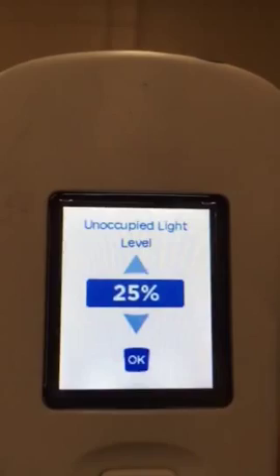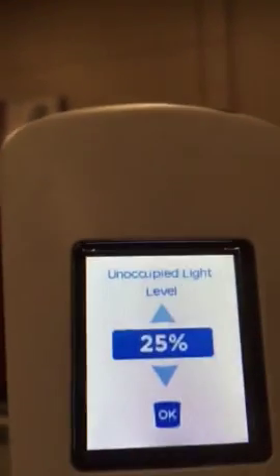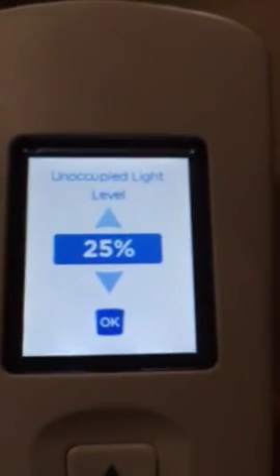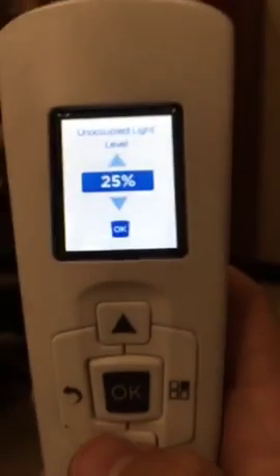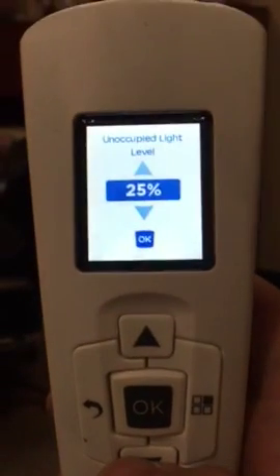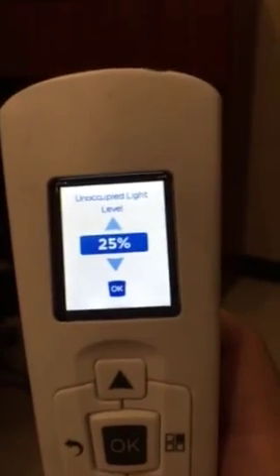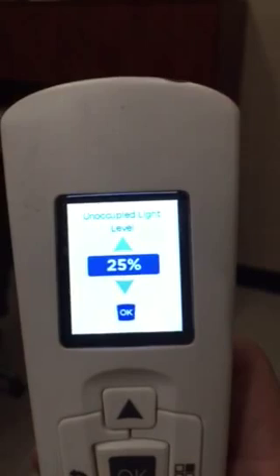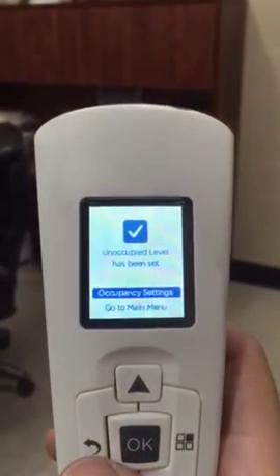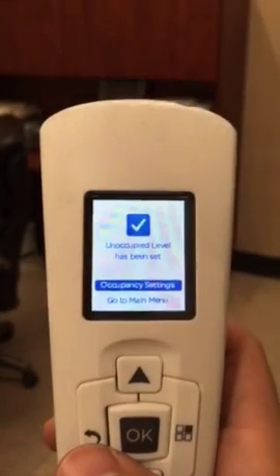It's going to say 'Unoccupied Light Level.' You'll also notice the four lights are dim, which means this has selected them. The unoccupied light level was set at twenty-five percent, to go into that after five minutes of no activity. But I came here about fifteen minutes later and the lights were still on, so I'm going to shut this off completely and click OK. The unoccupied level has now been set.